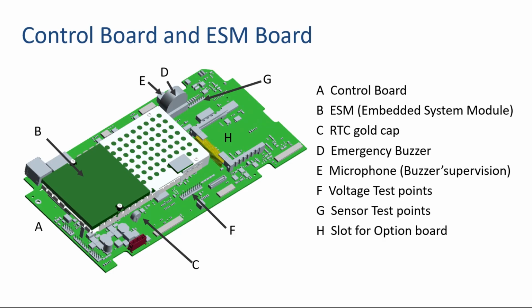The control board manages the analog output signals from all the sensors connected, then converts these signals to digital signals. It also generates signals to control the solenoid valves that are connected to this board. We will review the ESM in detail in the next slide. The RTC Gold Cap provides power for the device's internal real-time clock, also during the time when the device is not connected to a power source.